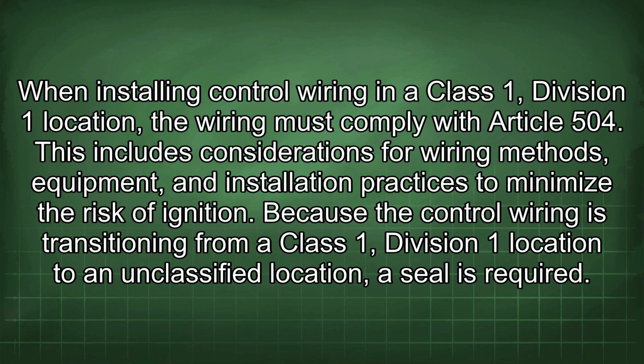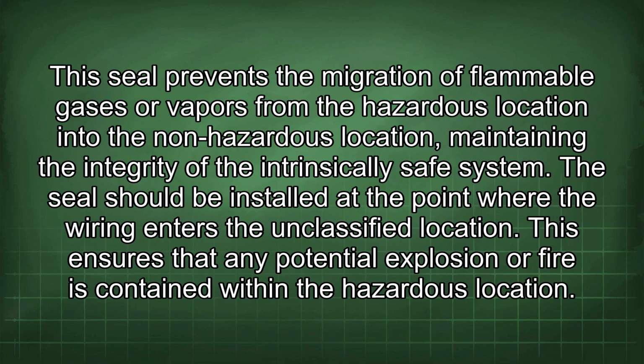Because the control wiring is transitioning from a Class 1, Division 1 location to an unclassified location, a seal is required. This seal prevents the migration of flammable gases or vapors from the hazardous location into the non-hazardous location, maintaining the integrity of the intrinsically safe system. The seal should be installed at the point where the wiring enters the unclassified location. This ensures that any potential explosion or fire is contained within the hazardous location.